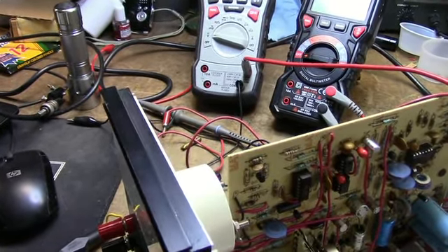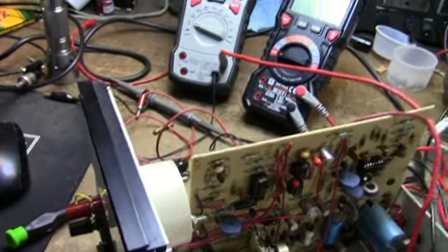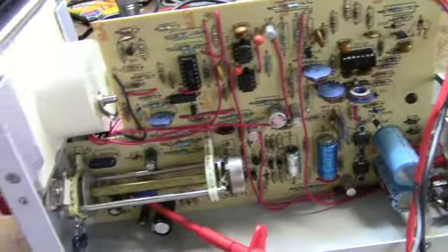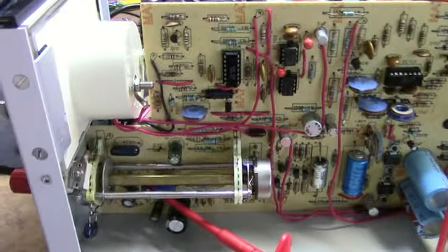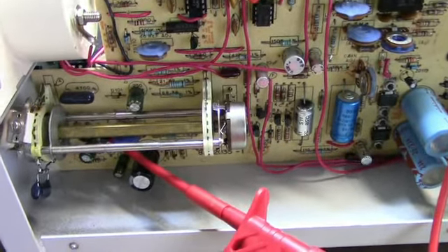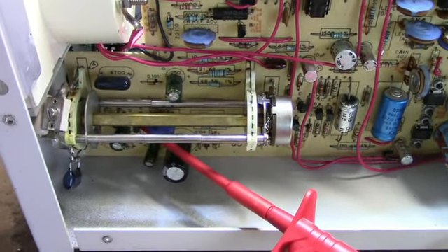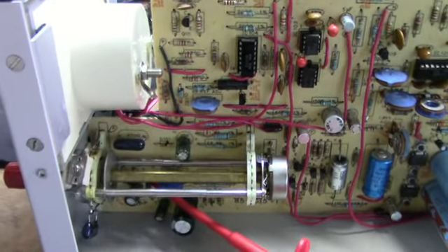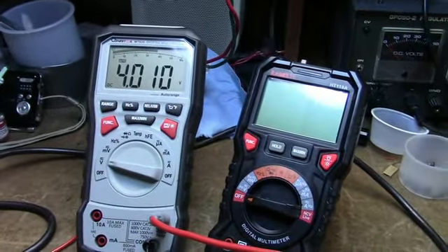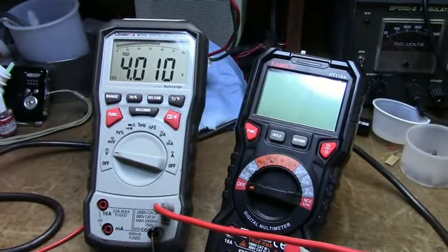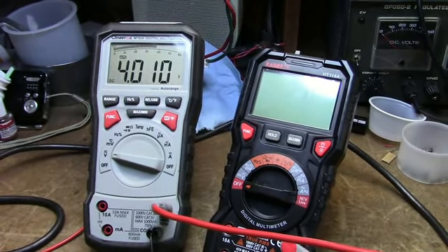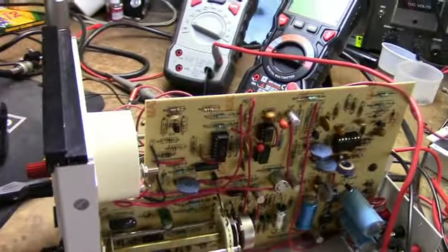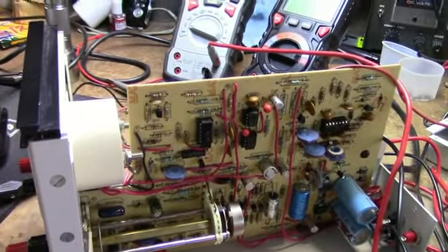Here's the calibration procedure according to the manual. You connect a small jumper across the input terminals, then connect a voltmeter between ground and the collector of Q102. You adjust the bias pot to 4 volts. This control's kind of touchy, but you can zero in as close to 4 as you can get it. 4.01 is close enough. It's an analog meter.